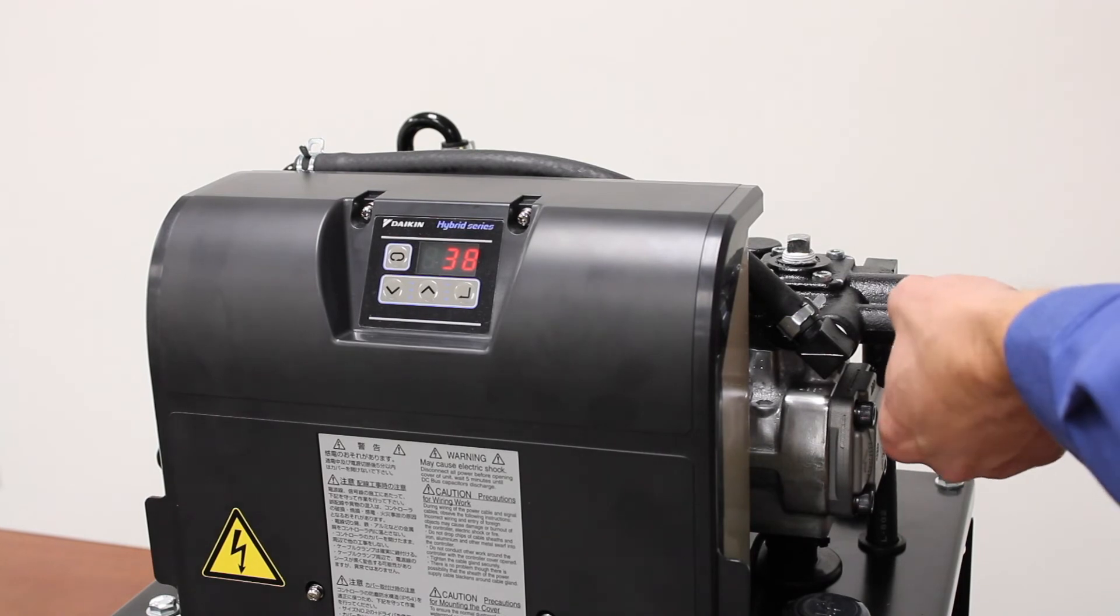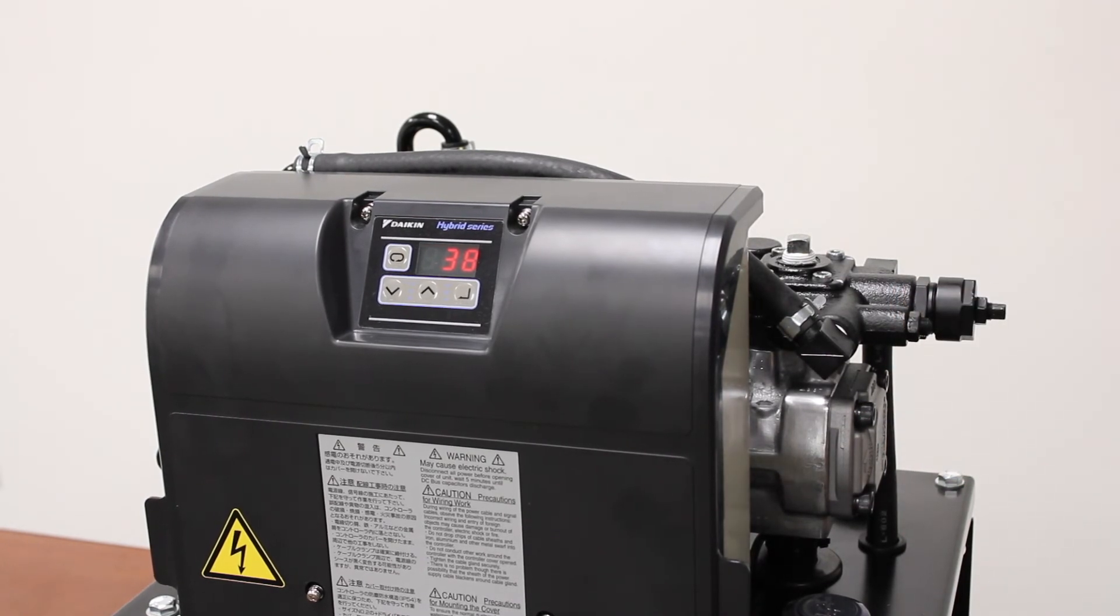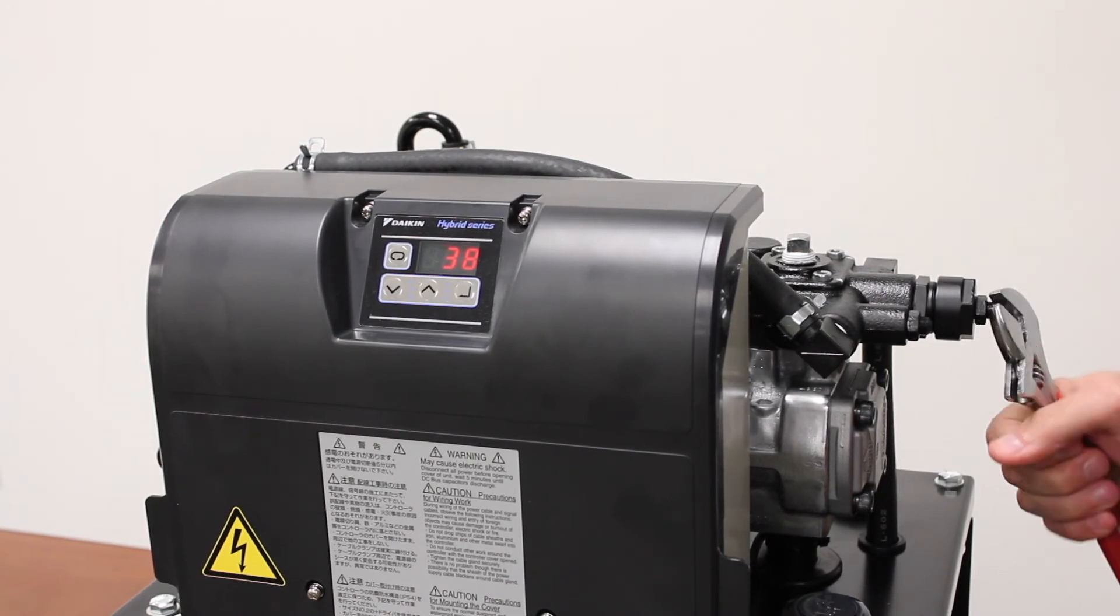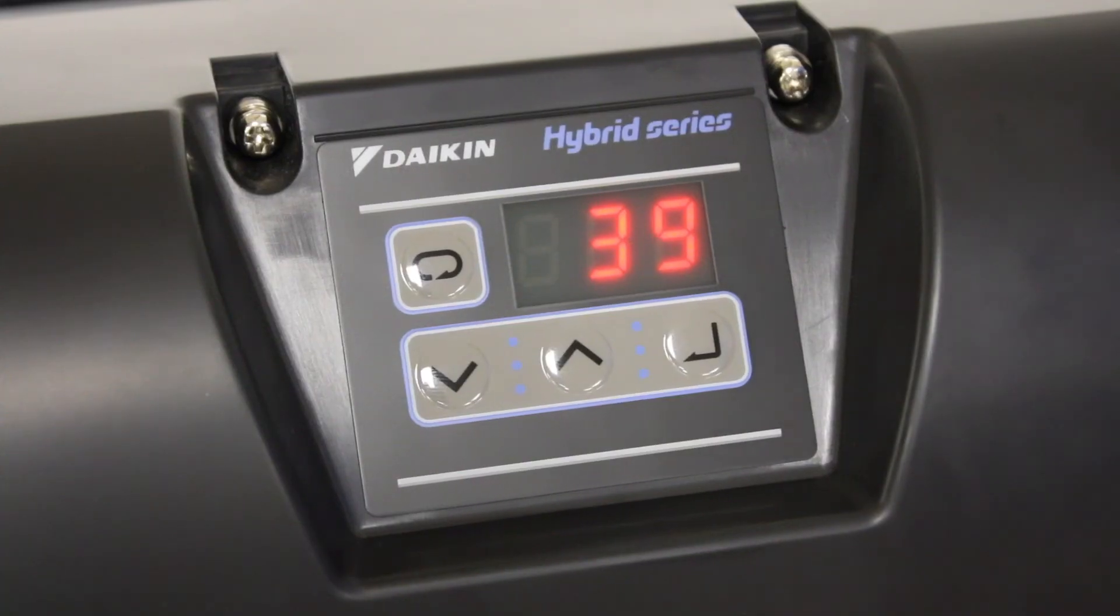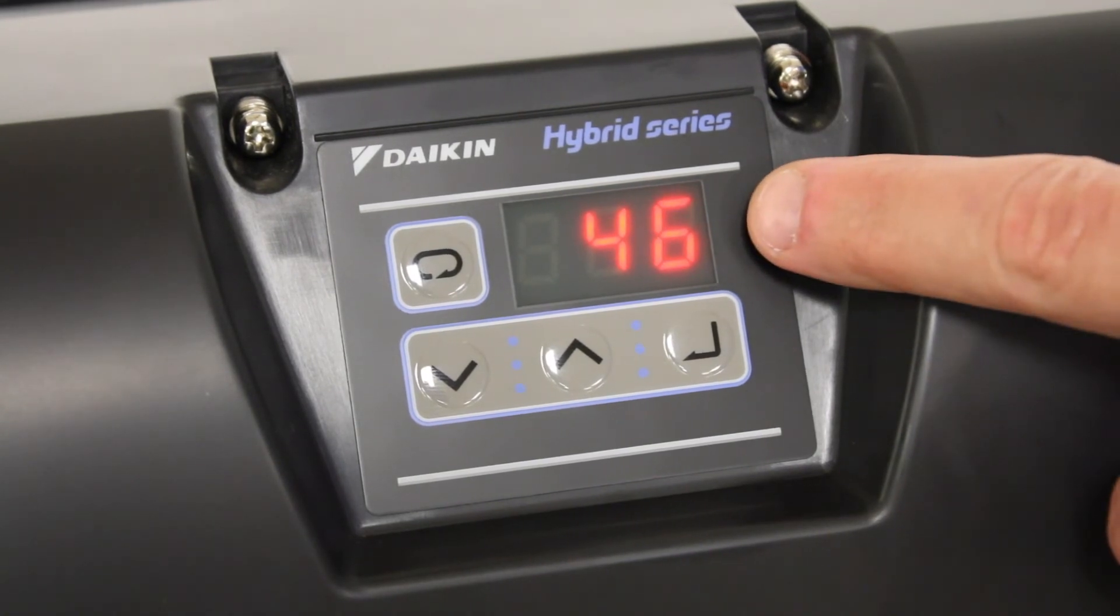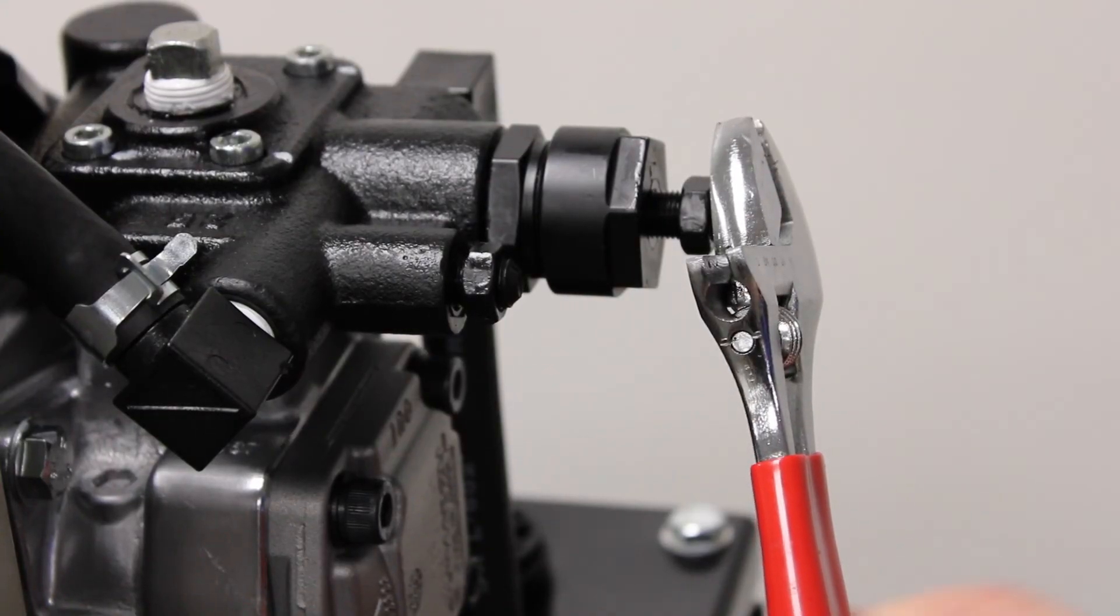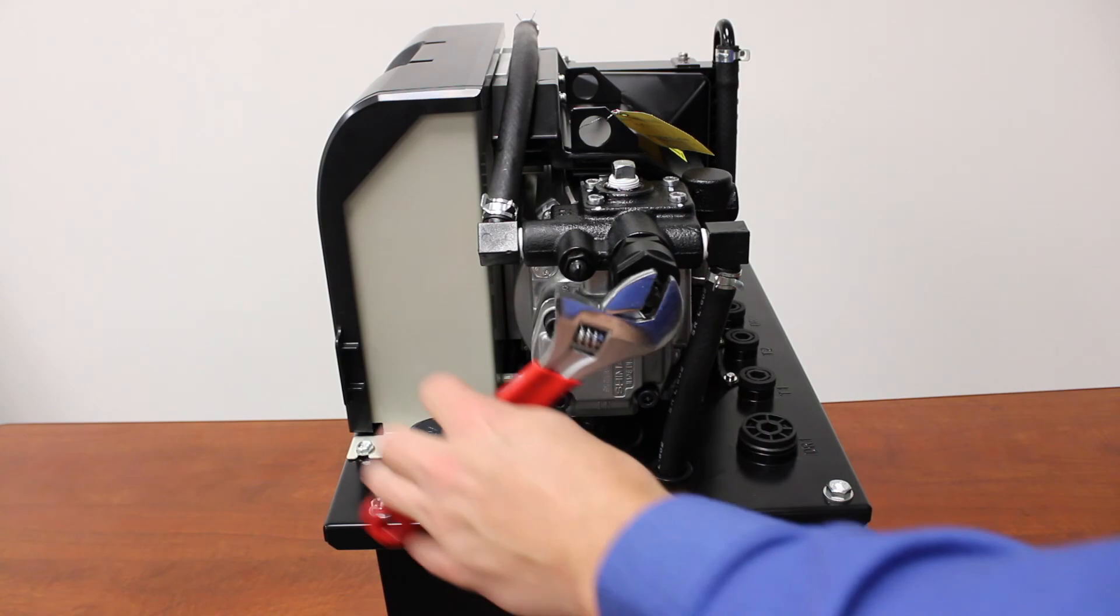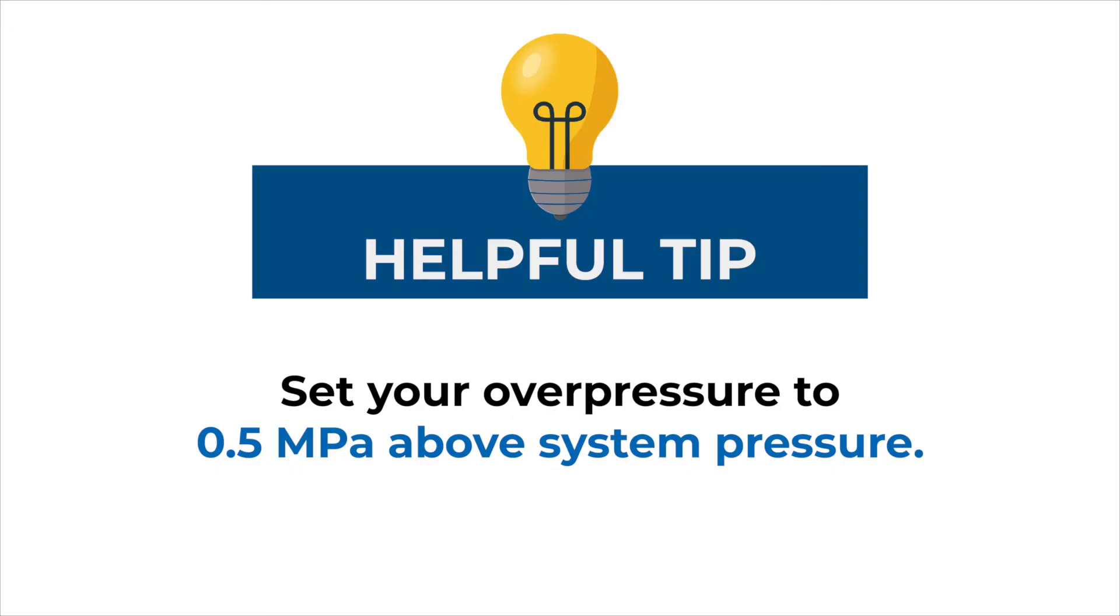Once there, we'll tighten down this jam nut, then we can set our over pressure relief. We will start turning this out counterclockwise until we see the value rise on our display. Right when the motor RPM starts to rise, you can stop turning counterclockwise and turn back in slowly clockwise till you come back to 38 on the screen.